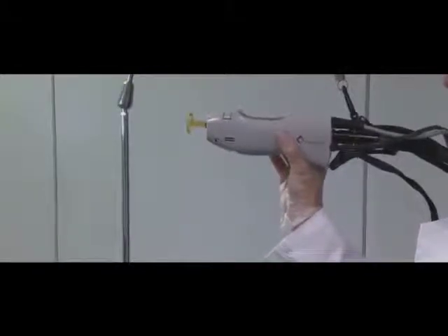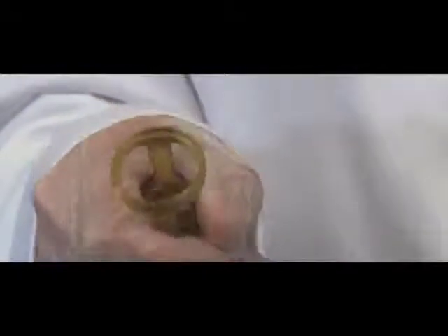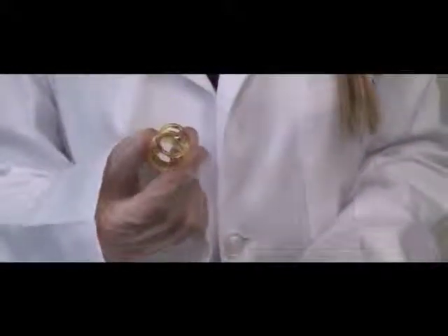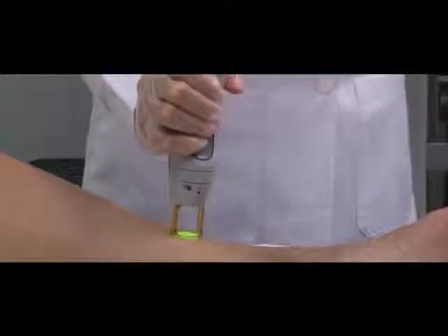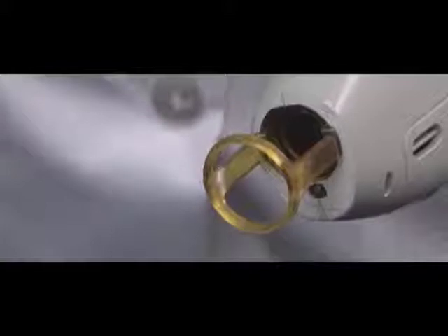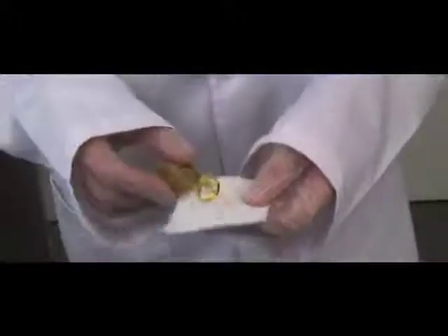Make sure your distance gauge is clean and has no black stain on it. If it is developing black stains, you may clean the end with a diluted bleach solution. Change your distance gauge every 200 to 300 pulses. A clean window and fresh gauge can be quickly and easily attached. Also during the treatment, keep the distance gauge free of any frost from the cryogen by quickly wiping every 30 to 40 pulses. And of course, clean with isopropyl alcohol or medical wipes between patients.